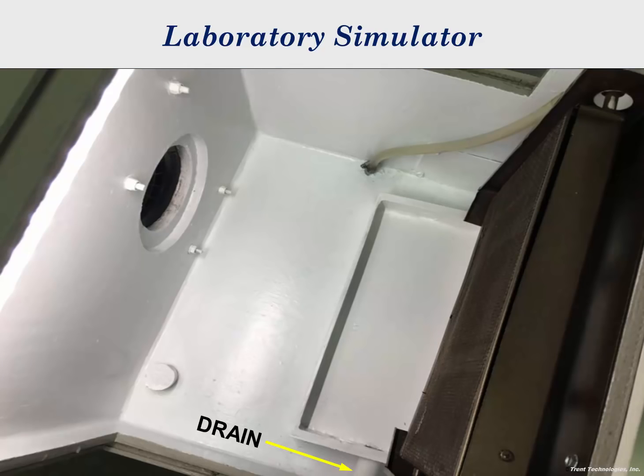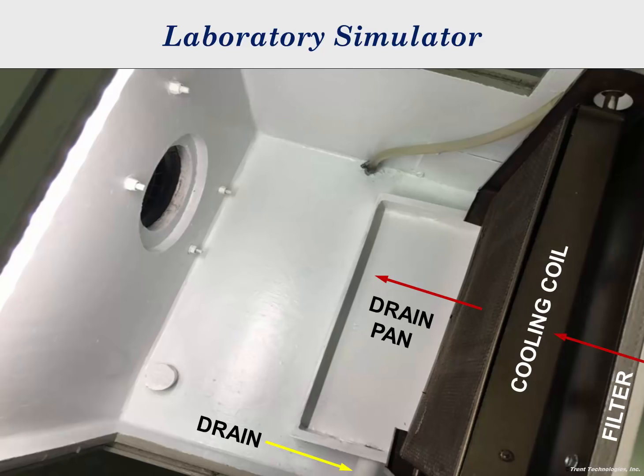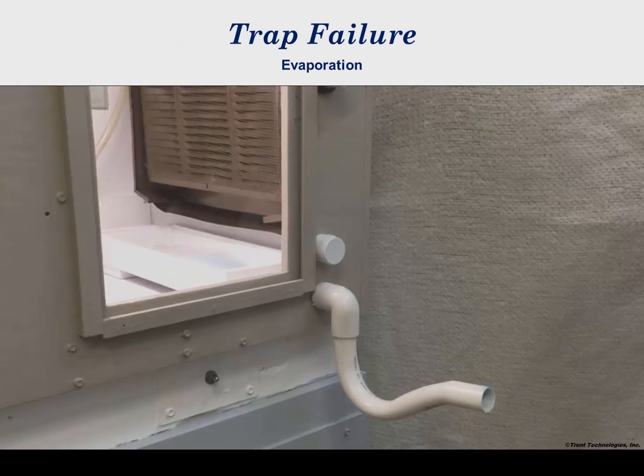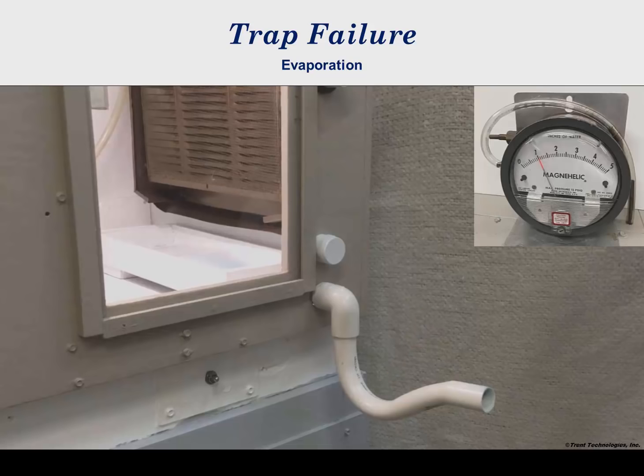Just as in a real system, air is drawn through the filter, the cooling coil, across the drain pan, and into the fan. With the best possible trap geometry, the effect of evaporation is illustrated with an empty trap. The laboratory simulator is being operated with a negative one inch of water pressure. Systems are often operated at this or more negative pressures.